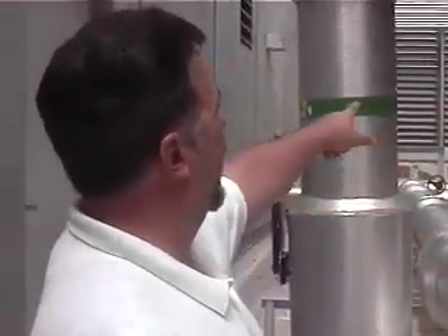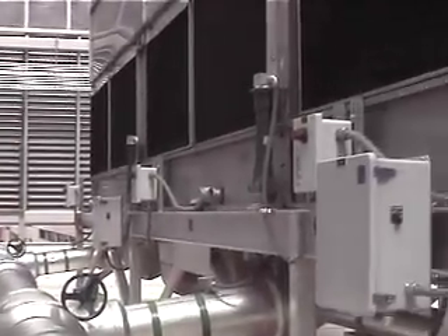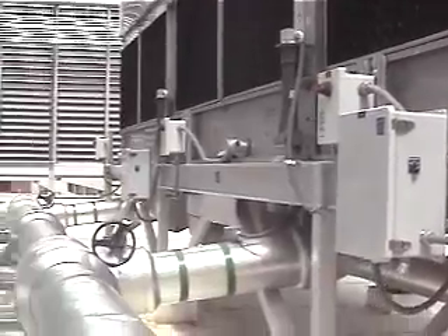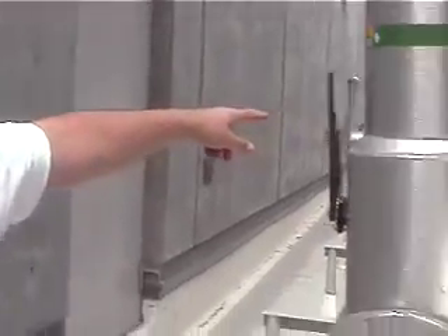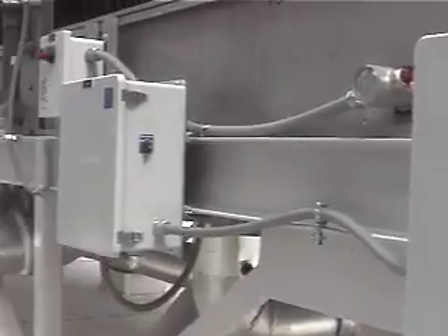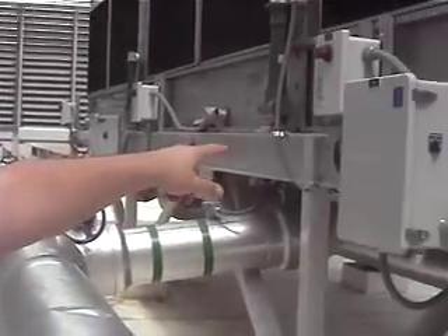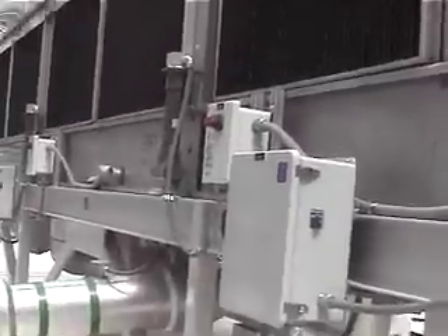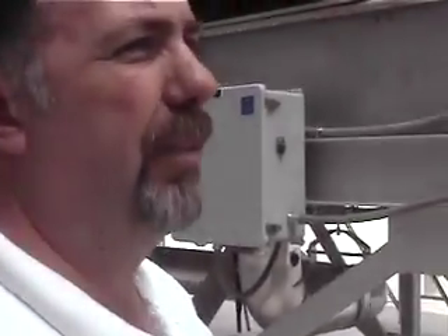So we've got the 3 cooling towers out here. Like I said, when we reviewed the graphics, they all act as 1 tower, 3 separate cells. You see all the pipes tied together, common sump, common supply coming back to them at the top there. You've got your sump heater in the cabinet for each tower. You've got a hand-off-auto switch on it. The smaller boxes there are for your relays for the level sensors.